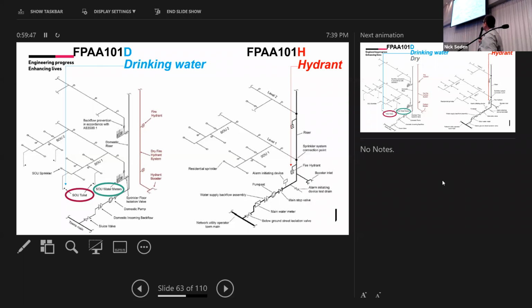then the other part of the D system is the dry. So there is the dry system from the hydrant booster. It still has the infrastructure, however, it doesn't have, if I go through every single valve, from your water meters, your stop valves, your pump sets, your alarms, it hasn't got all that infrastructure. So it's still got that going up in your stairwells, however, not within the units themselves. So they are two completely different systems.